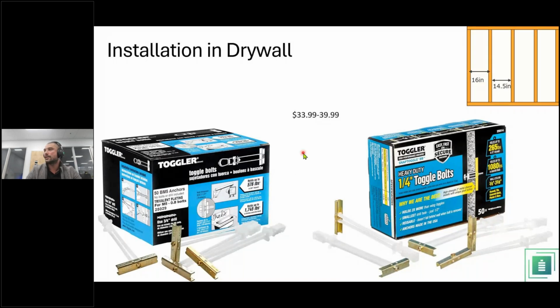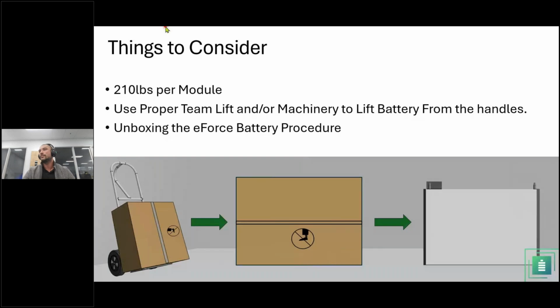All right, installation, floor mounting. Things to consider: each battery is 210 pounds per module, so it's a big boy, 9.6 kilowatt hours. Make sure you're using a proper team lift, at least a minimum of 3 people. I've personally installed this with another person, but in order to comply with OSHA standards, we recommend using 3 people, or a special type of machinery that suspends the battery.